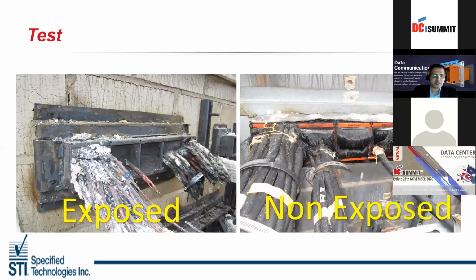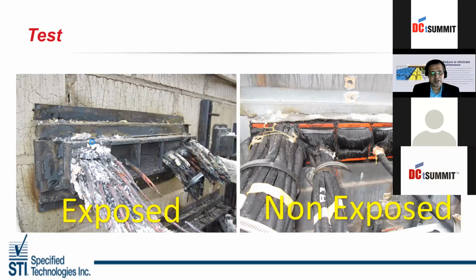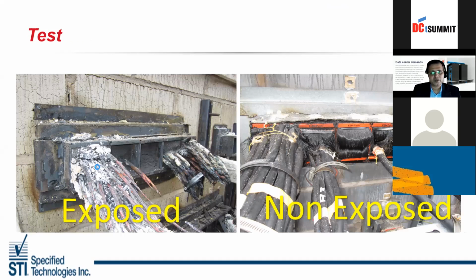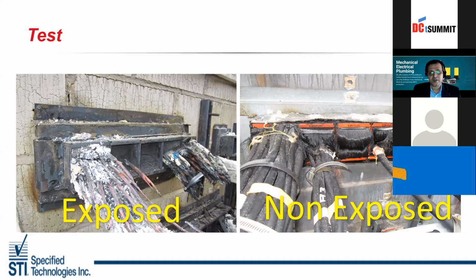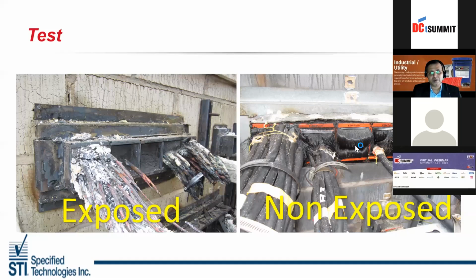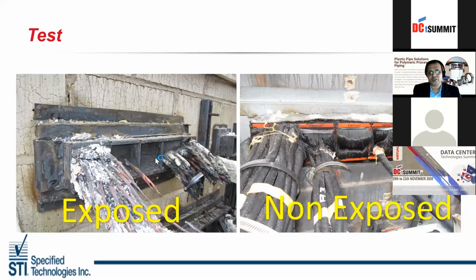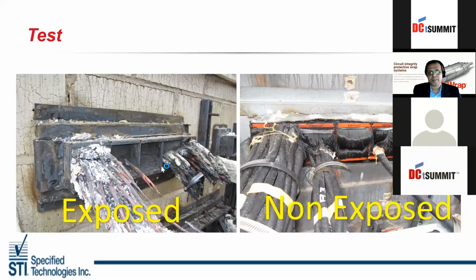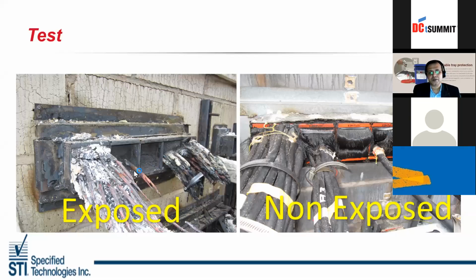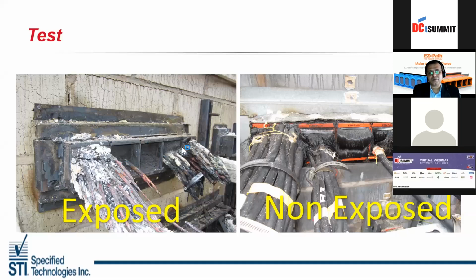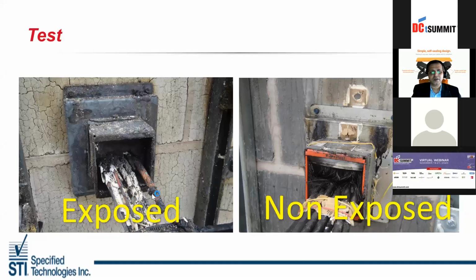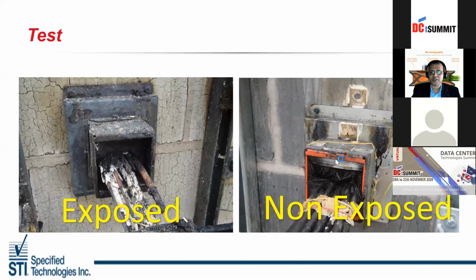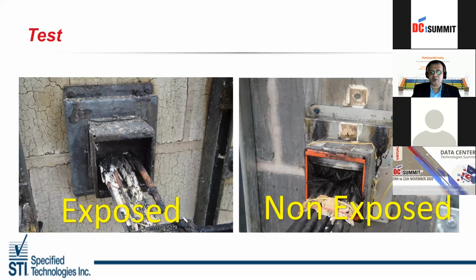These are the test scenarios where we have done some tests. This is the exposed side, and this is the unexposed side. You can see the difference. You can see 1, 2, 3, 4. You have 1 cable, and you have a 0 cable here, and you can see the difference. The fire has not traveled to this part. You can see that this is completely burnt, completely damaged. Scenario here, the single EZ path is completely exposed, and this is the non-exposed side.